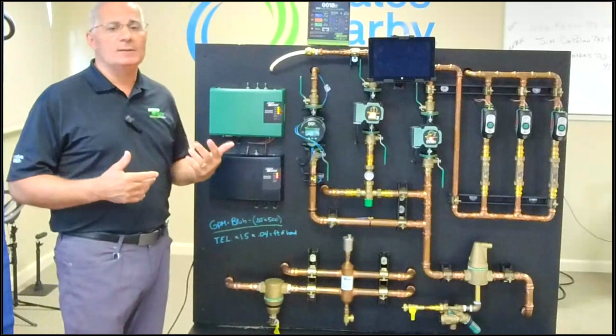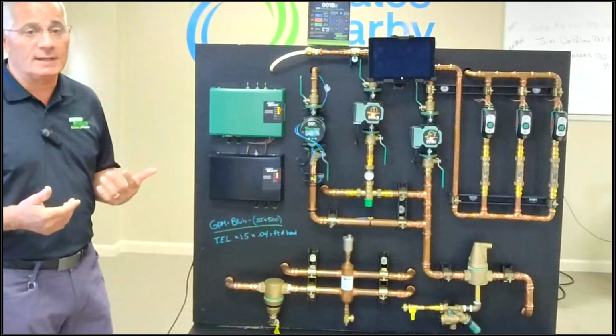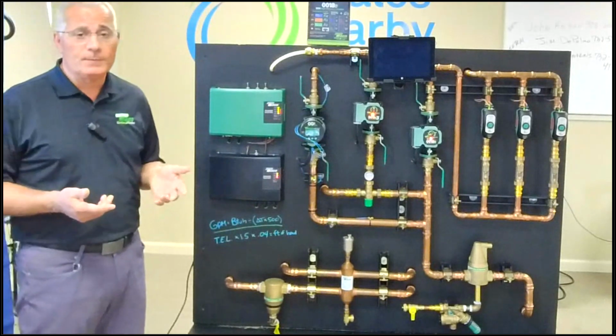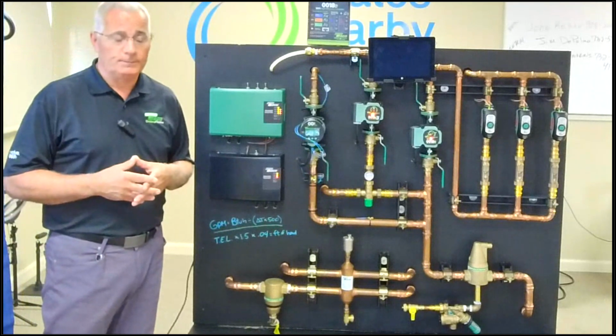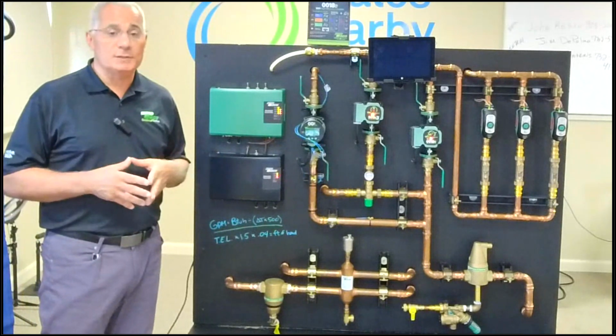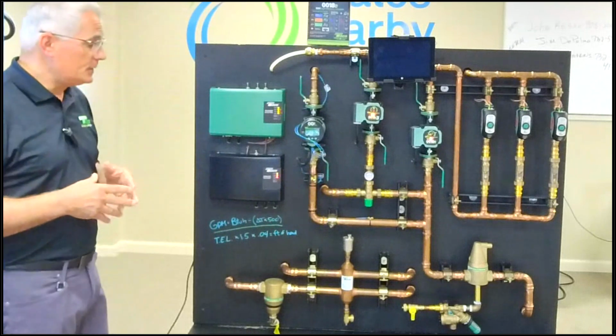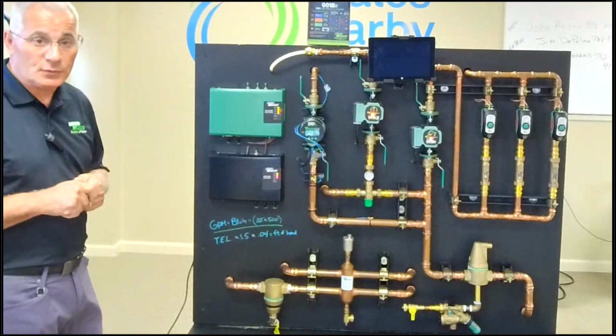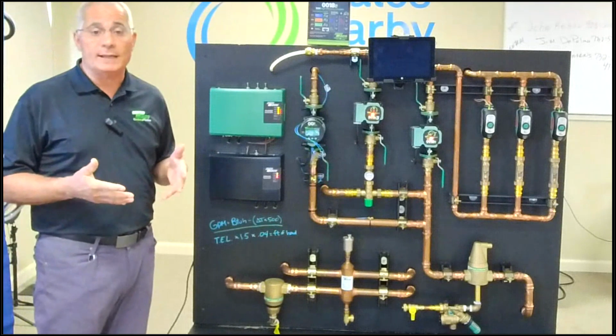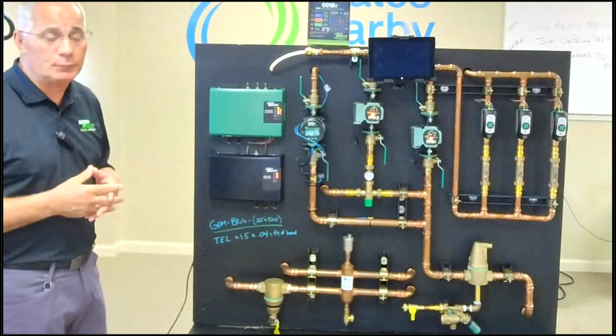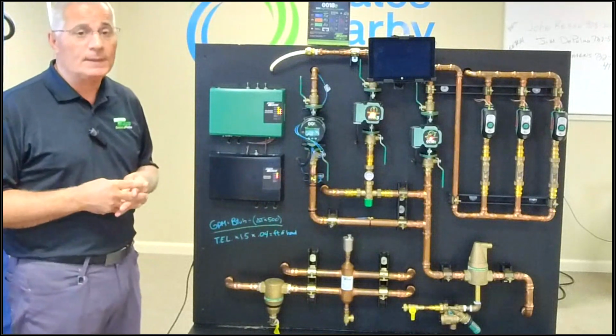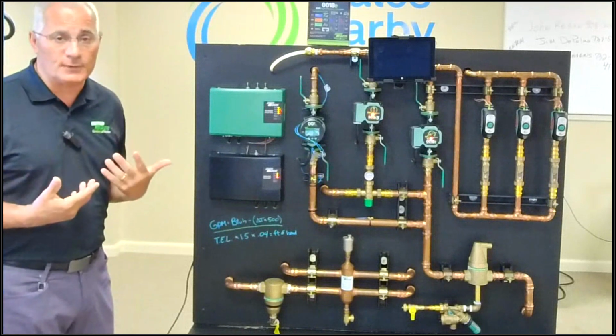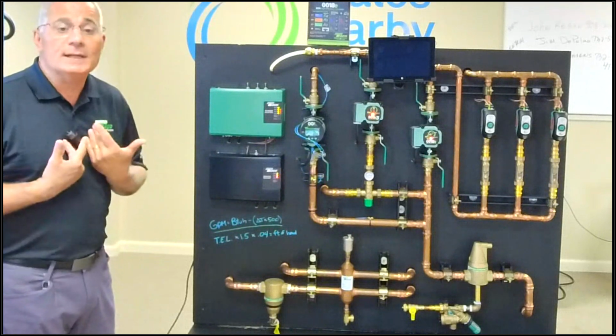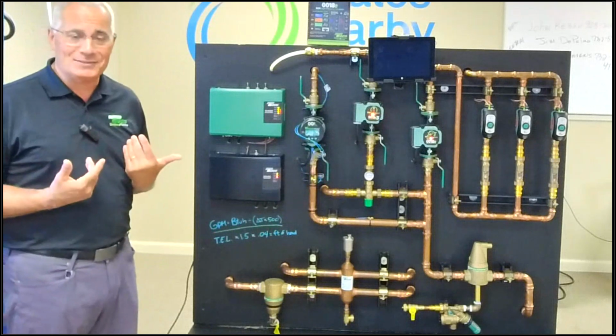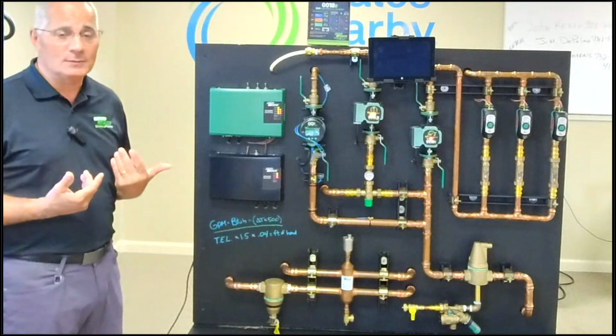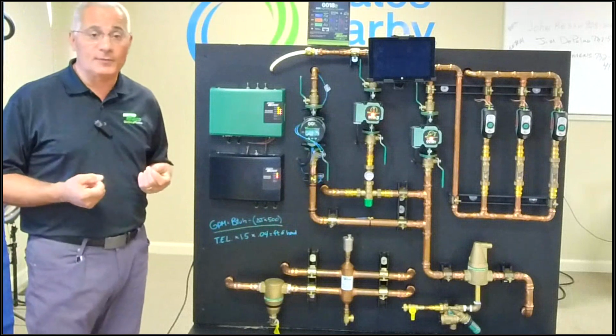So what do we normally see in our territory here in the New York, New Jersey area? We're taking out cast iron boilers, we're putting in a condensing boiler. A couple of things we should address is water treatment, which is something we have talked about. So if Robbie's going to do a job, he's going to take out a pre-existing cast iron boiler in his house. He wants to pre-treat the system first. We do not sell these products, but we do sell condensing boilers. We want to make sure we're protecting the boiler. So we're going to pre-treat that system first.